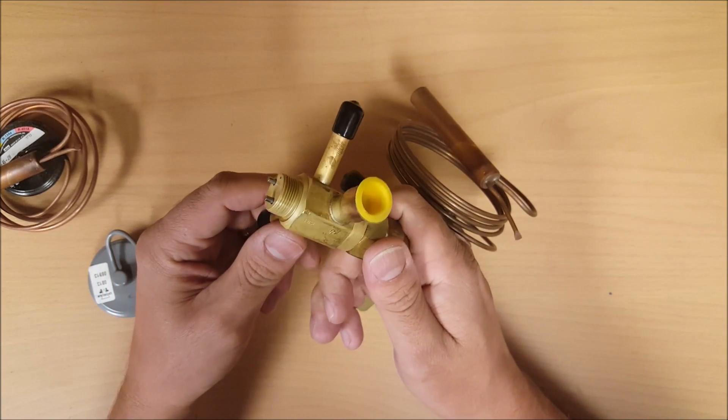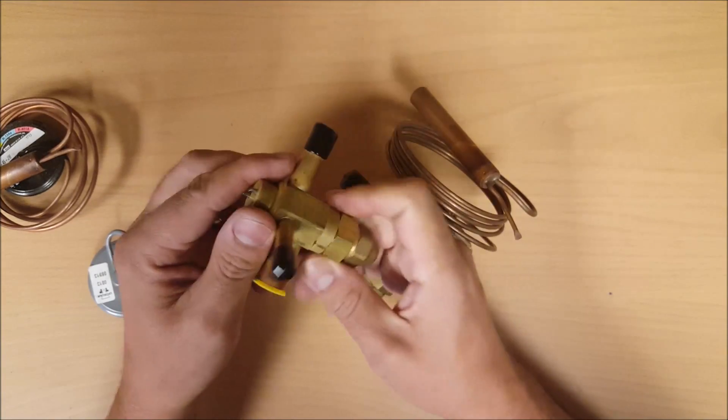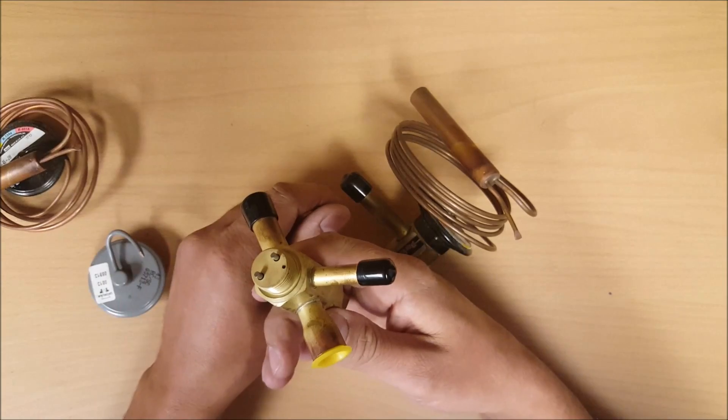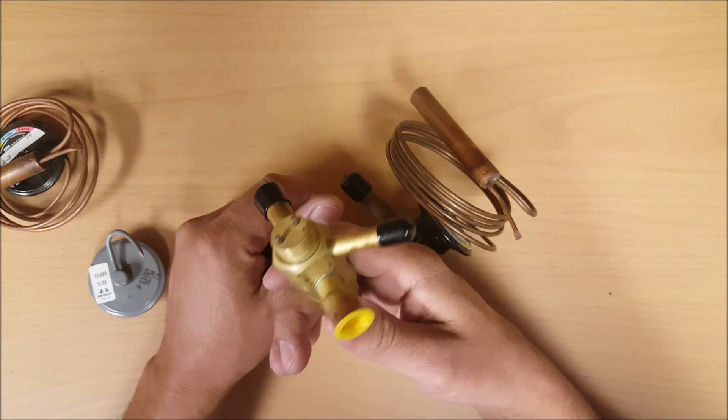Most likely you won't be able to get an exact match on your valve, but you can get a range. Let's just say 6,000 to 12,000, which would be half ton to one ton valve rating. That's what you would use on a 12,000 BTU evaporator.